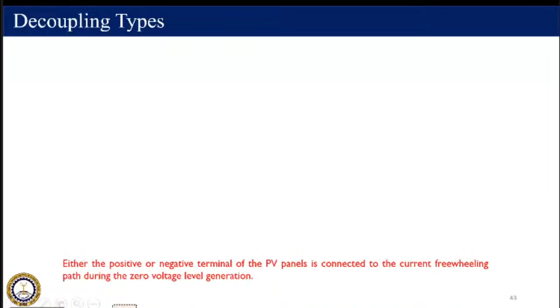So what is this decoupling? Decoupling is basically disconnecting the PV from the grid during the zero state. Zero state means freewheeling state, during which the PV is disconnected from the grid. This is going to reduce, or minimize, the current.